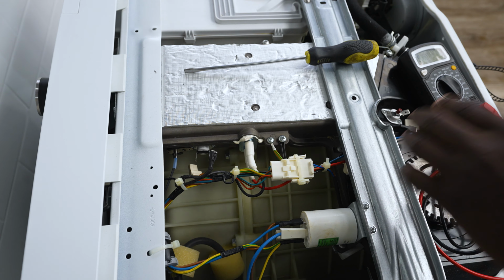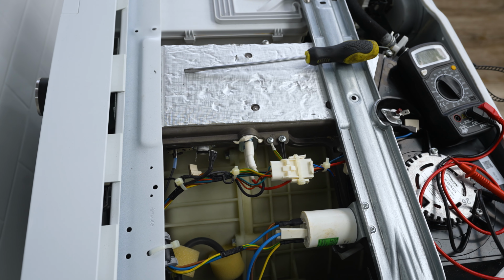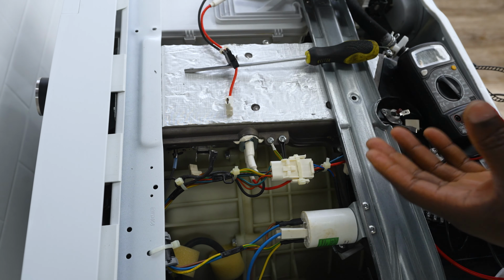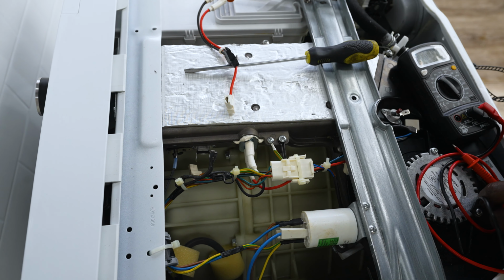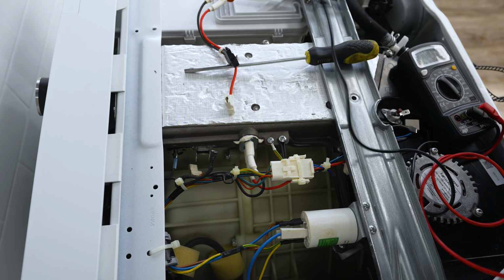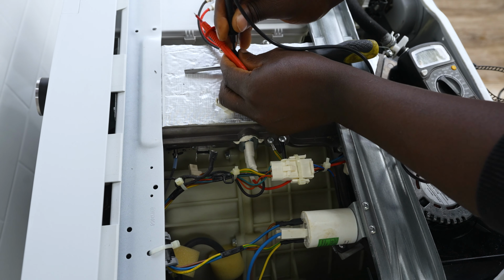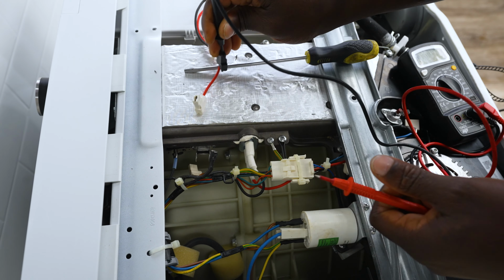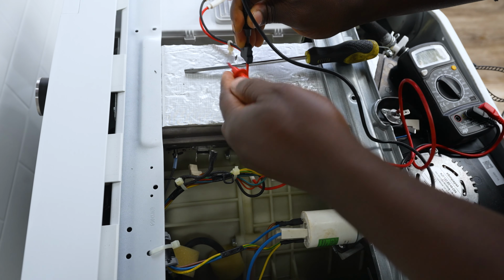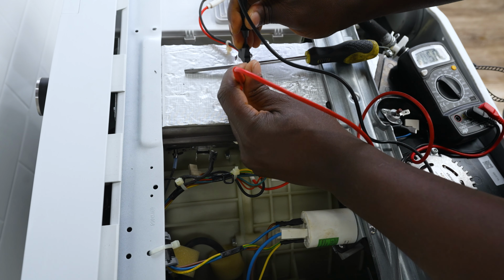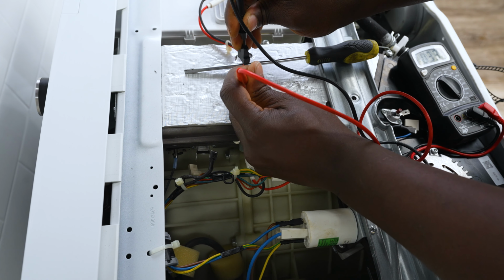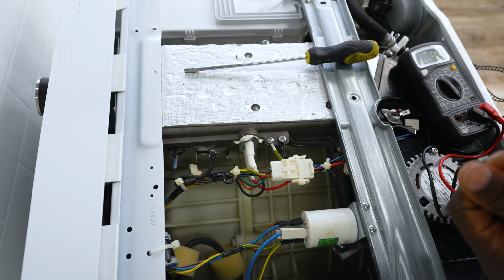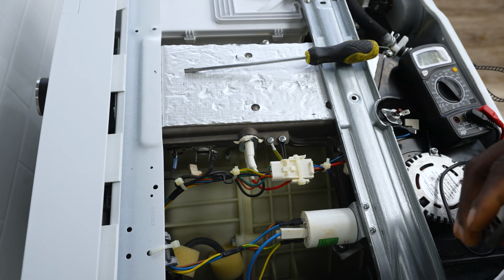I've got another heater here just to show you for comparison, because a lot of people get hung up on how much resistance there should be. Let's just see — the first thing we want to check is whether there's any continuity. This is another heating element I've got lying around, and I'm going to test that for continuity, and straight away I've got continuity. So that means this heater is working, but the one on mine is not working.